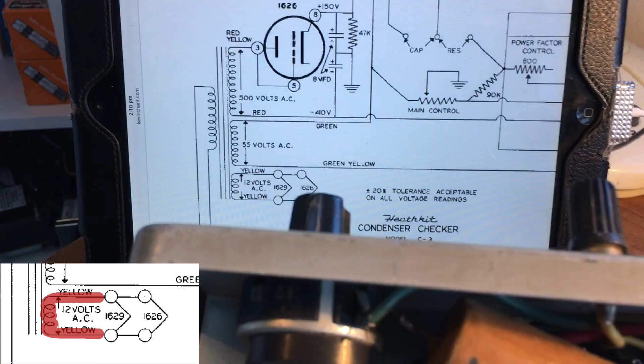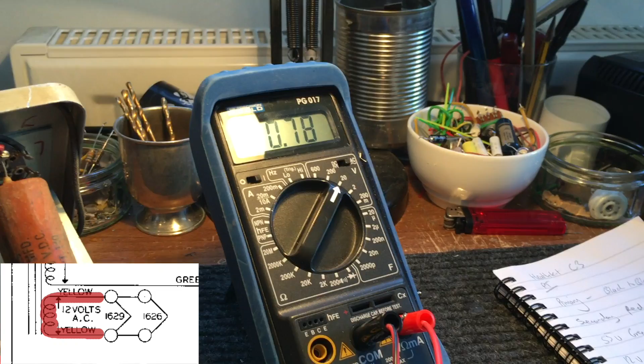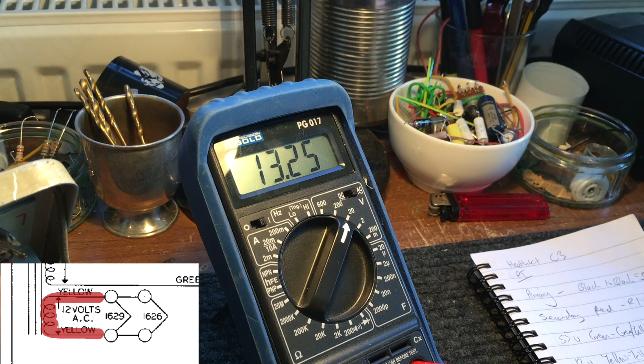And the final one is the 12 volt winding, yellow to yellow. Connections made just as before. Switch the meter to the 20 volt range because I'm expecting 12 volts. On it goes. As I said before, they're all going to be higher than expected because the tester is unloaded, i.e. there's no valves in it, no current flowing. 13.2 volts AC. Perfect. Right, so all of those tests have now confirmed that our mains transformer is working as expected.